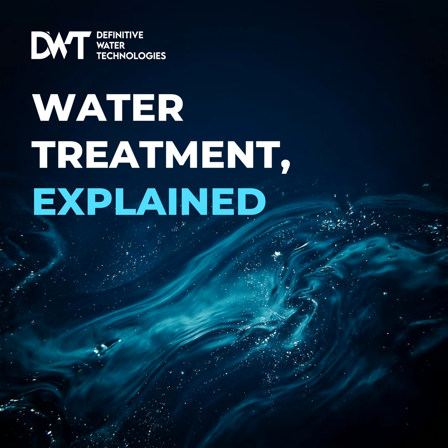I get that it's great for very low flows or viscous liquids, but why on earth would a smart engineer deliberately choose a pump where the core component is a scheduled consumable? I know, it sounds crazy. It's literally designed to actively wear out from friction, and the pressure rating is tiny, like a few bar at most. Why buy a pump that destroys its own parts? It sounds totally counterintuitive.